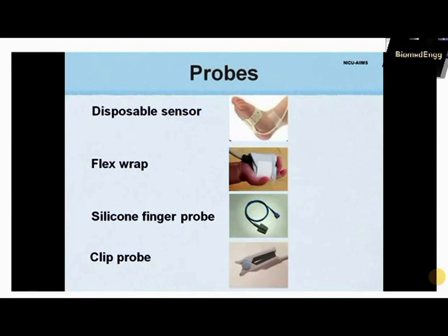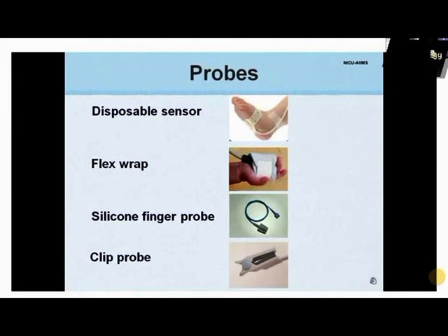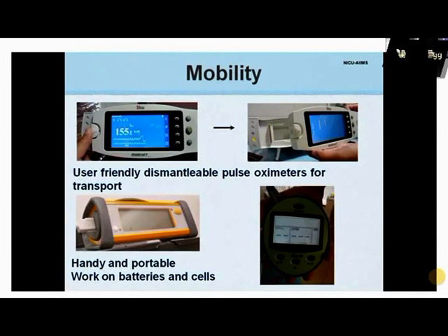There are different types of probes available. Disposable probes are available though expensive. Flex probes ensure good fixation and safety in neonates, with a life of 6 months. Finger probes are sturdy and last at least 1-2 years. Clip probes can be applied over a finger but are difficult to use in neonates. Some models allow the display panel to be dismantled for transport, and handy portable pulse oximeters work on batteries, making them ideal for transport.